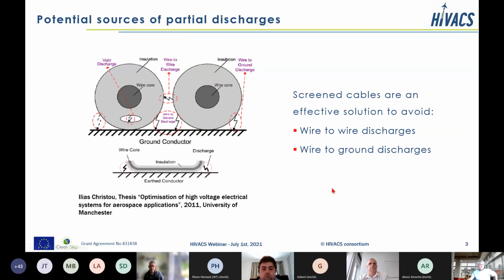Regarding partial discharge, we have different sources for partial discharge. So partial discharge could appear in the air gap between wires, or between wire and ground, or in voids inside the insulation. To avoid the partial discharge in the air gap between the wire and ground, we may use screen cables, as those contain the electrical field inside the insulation, and hence partial discharge may only occur in voids inside the insulation.